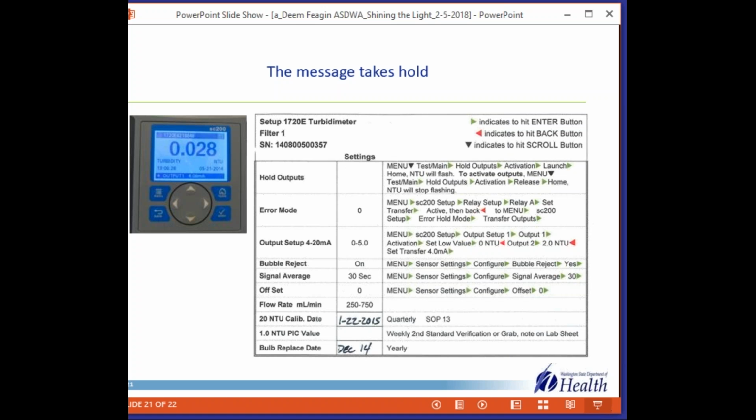Okay, so some more questions. Thank you on the pH questions. So for pH, do you use or require the use of an internal calibration check, an ICC standard, for verification of instrument calibration? We have not finalized what we want to tell everybody to use. So we are looking for this type of input before we write it down. With turbidity, we actually came up with, here are our recommendations.